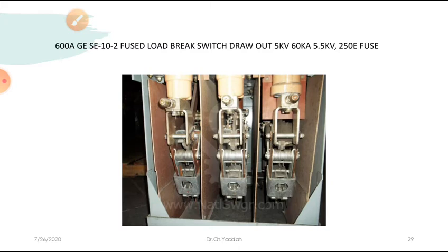Have you ever seen what it has inside? It has a spring. That means you always have to remember that electrical switches should be operated very quickly, otherwise there is a possibility of an arc taking place between the two contacts. Why? Already you have seen, when the switches are opened very slowly, normal current is flowing at 0 plus time, and then a moment later the switch is opened. So during this period, the gap between the two contacts is very small.